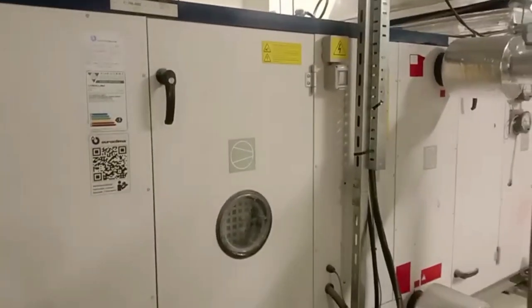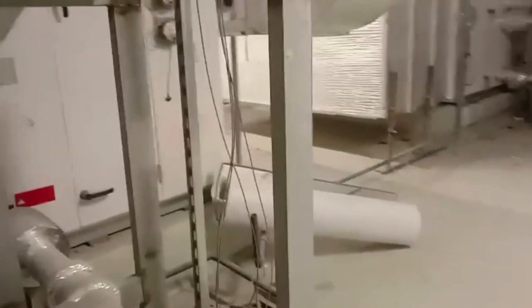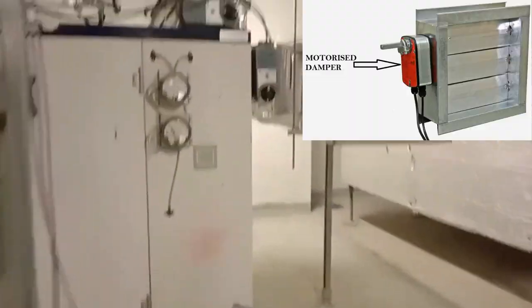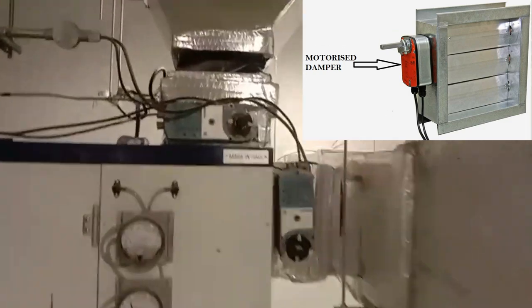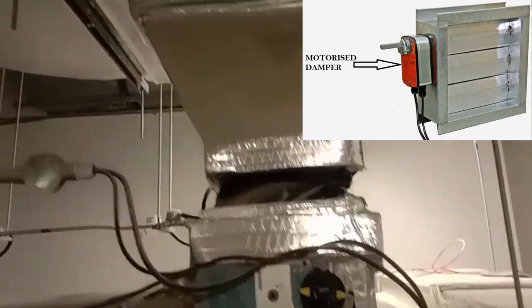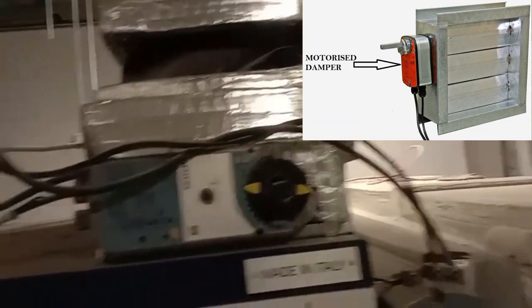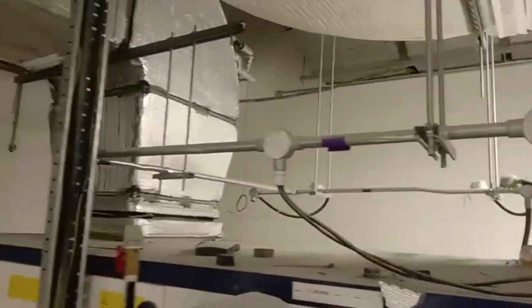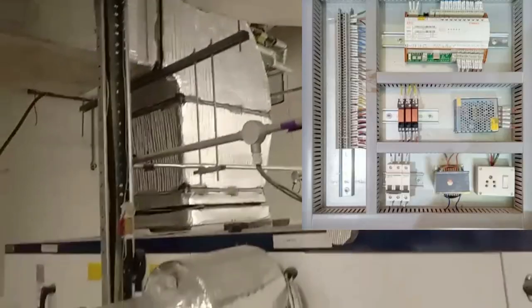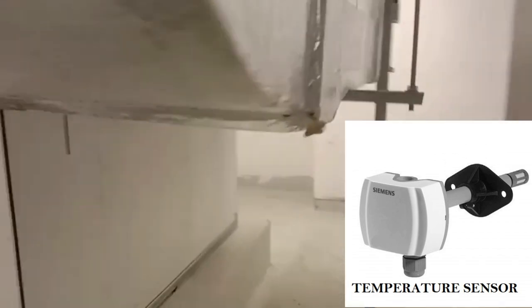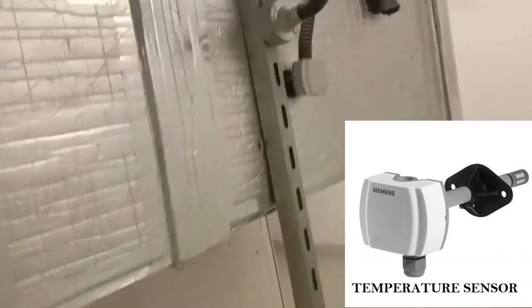So I'll take us now to the field devices for the BMS system. We have all the different field devices that have been installed, which I started with motorized dampers. As you can see, we have the cables, which are also installed. We've terminated them as well to the motorized damper. It's moving from here, goes to the DDC panel. And then as well we have some temperature sensors and some pressure switches.